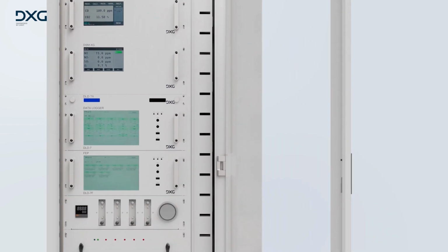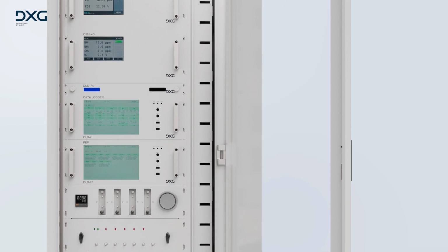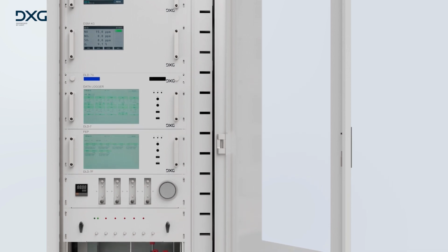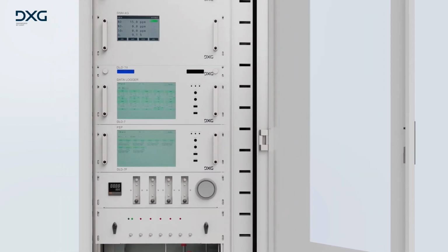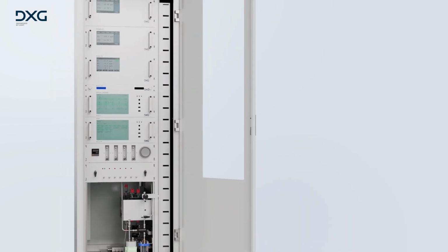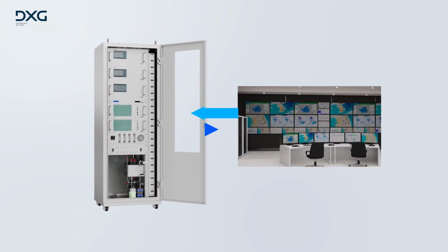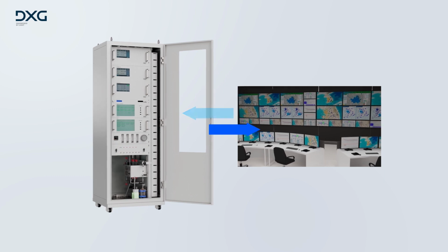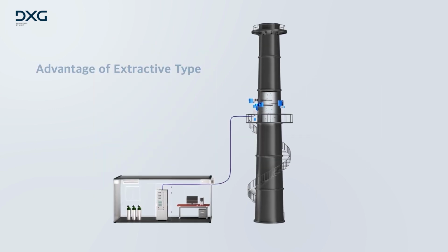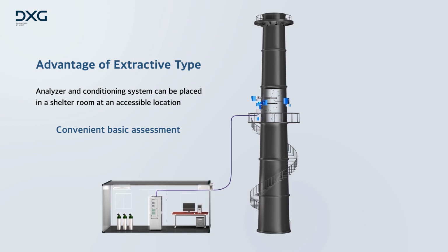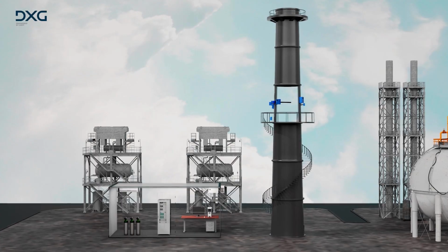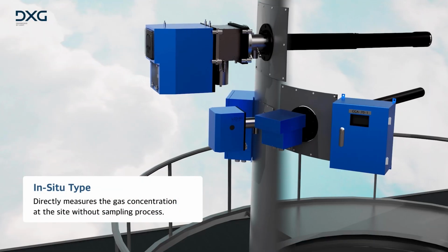Finally, measured emissions data is transmitted to the Environmental Regulatory Agency through the data logger. For plants with multiple chimneys, the data collected by each data logger is first collected by a data acquisition system, and the integrated data is transmitted to the Environmental Regulatory Agency. The most significant advantage of the Extractive system is accessibility. Analyzers and the conditioning system can be placed within a shelter room at an easily accessible location, making basic assessment of the system very convenient. The In-situ system directly measures the gas concentration at the site without a sampling process.